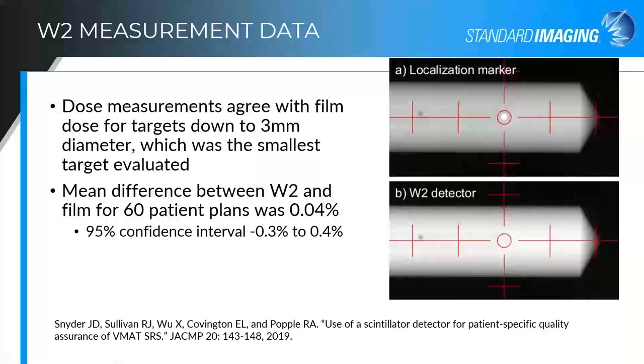The W2 has also been used for patient-specific measurements. A publication from the University of Alabama at Birmingham, Richard Popple's group, looked at agreement between W2 and film measurements for varying RapidArc treatments, treating targets down to 3mm diameter, with excellent agreement within the variability and uncertainty of film measurements. An image from that publication shows the scintillator inside a lung-equivalent phantom chamber plug — the scintillator tip is very hard to locate because it's water equivalent. We provide a dummy fiber with a BB to help locate it in treatment planning or imaging alignment for measurement QA.